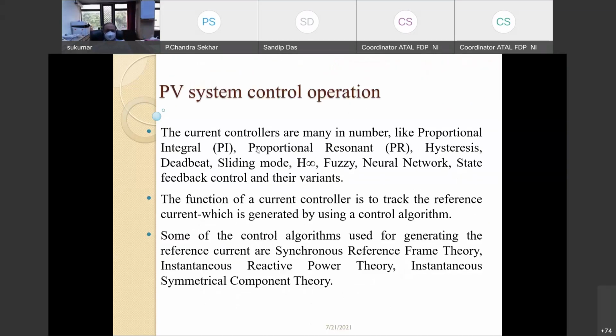Now, this control operation can be done with a simple PI controller, or with new approaches of control like fuzzy control, neural control, sliding mode control, and many other things. Also, a new philosophy of proportional resonant control can be used in your control schematic. The function of a current controller is to track the reference current which is generated by the control algorithm. So either we can go for PI or we can go for PR. And the control algorithm required is to generate the synchronous reference frame, and the reactive power can also be produced, and the symmetrical component theory can be extended.